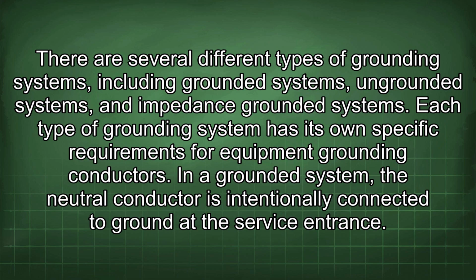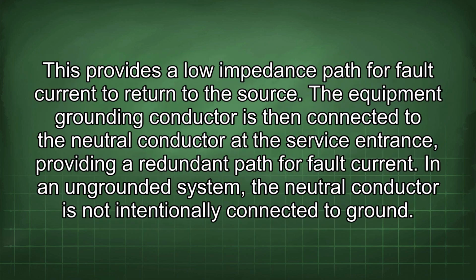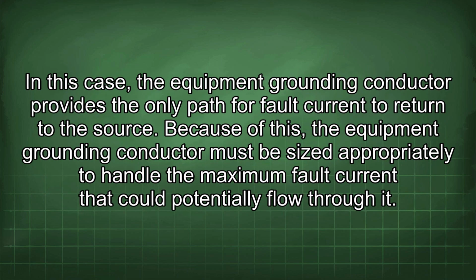In a grounded system, the neutral conductor is intentionally connected to ground at the service entrance. This provides a low impedance path for fault current to return to the source. The equipment grounding conductor is then connected to the neutral conductor at the service entrance, providing a redundant path for fault current. In an ungrounded system, the neutral conductor is not intentionally connected to ground. In this case, the equipment grounding conductor provides the only path for fault current to return to the source.